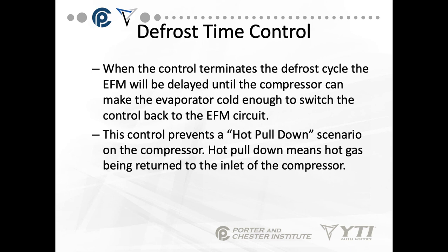This prevents a hot pull-down scenario on the compressor. Hot pull-down means hot gas being returned to the inlet of the compressor. The cold refrigerant gas coming back is what cools the compressor, so we don't want hot gas being returned.